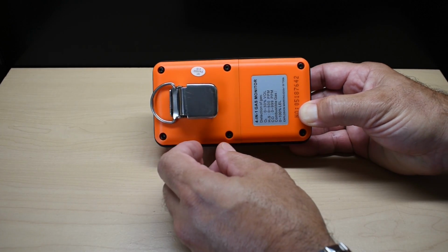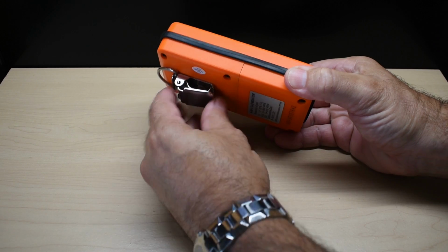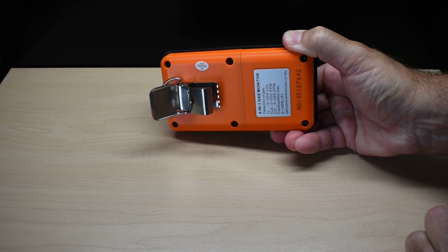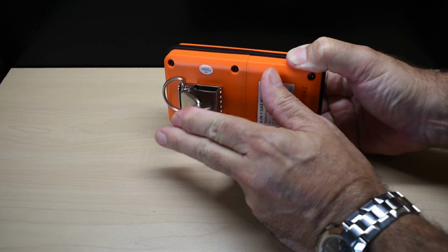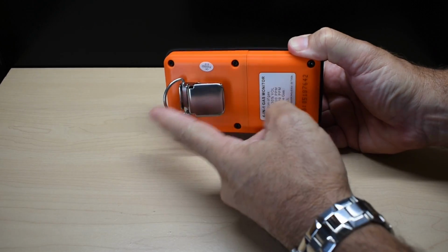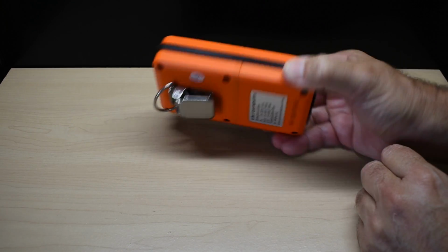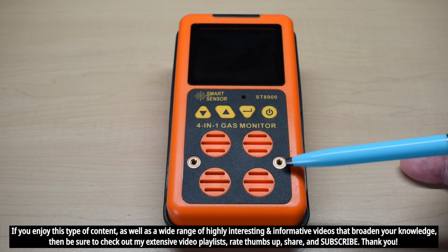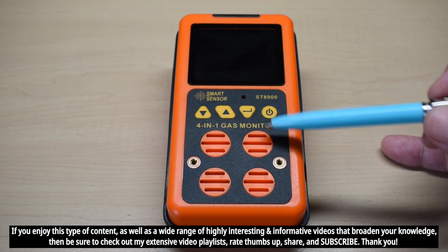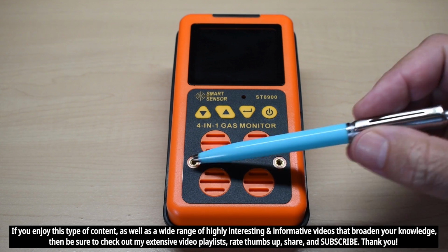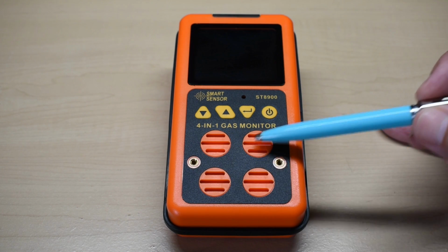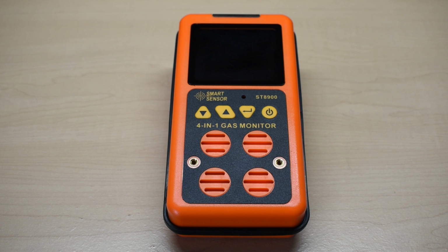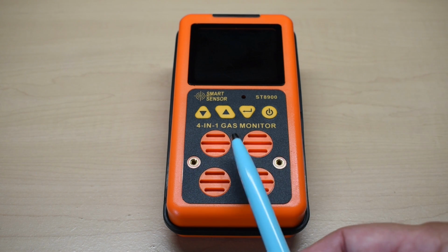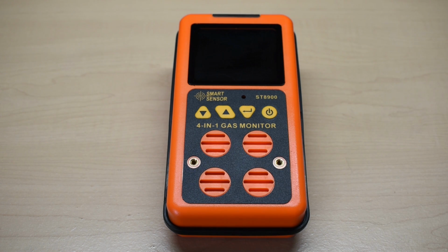Very nice stainless steel clip here. Secure it right to your uniform. Clamp it back down, and you also have this connection here if you want to hang it on a wall. Right here you can see 2 brass threaded inserts. The purpose of that was before this left the factory, it was calibrated. It just holds the test source gases directly over these sensors for the calibration procedure. This unit can measure oxygen, hydrogen sulfide, carbon monoxide, and all types of flammable gases.